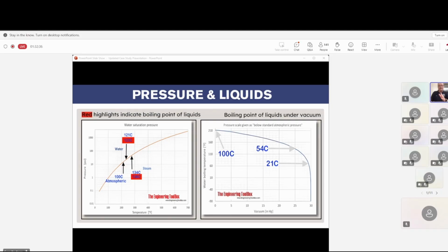The chart on the right is what happens under vacuum. Now, if you have a pre-vac cycle or the ability to run a vacuum in your autoclave, this is going to be absolutely critical. What happens here is you see the vacuum and how it goes down. At 100, which is atmospheric, again, we're at 100 C. And then as your vacuum gets pulled, most autoclaves should be able to pull between 25 and 29 inches of vacuum, depending on how much your water supply and how good your pumps are. But they should at least get down to 25.